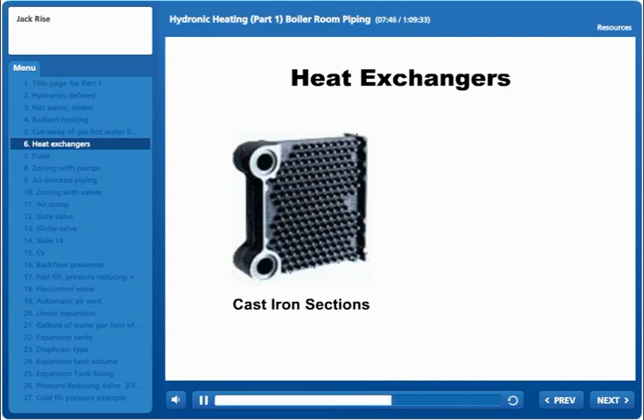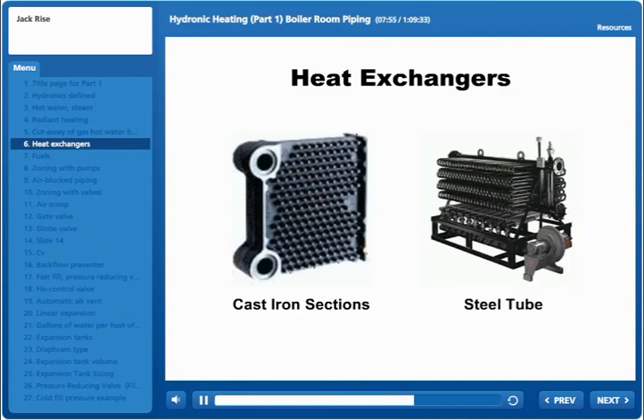that's cast iron. Very, very common. These are vertical cast iron. They can lay down flat. Like I said earlier, Hydrotherm makes those. They call them pancake sections. Here's another very common type, steel tube heat exchanger. The water runs through the inside of those tubes, and the burners, you can see the burner on the bottom, that looks like either a gas power burner or an oil burner. I can't tell from the picture, but that heat is going to be taken off by the water in those tubes. And again, the more heat you take off, the more efficient the boiler is. They do make residential steel tube boilers, but they're not real common. Okay, mostly you'll see steel tube boilers in commercial work.